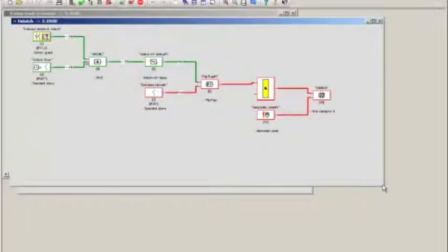And so the logic that I have looks a little complicated, but it really isn't all that bad. What's important is that the unlatch right now is red. That means there is no current flowing to the solenoid. In order to do that, I need to turn on this flip-flop. And we've talked about flip-flops earlier. Flip-flops have a hold condition and a set condition. The hold condition is latched in by the flip-flop when the set occurs. And in order for the set to occur, you can see down here, that is my input S61.